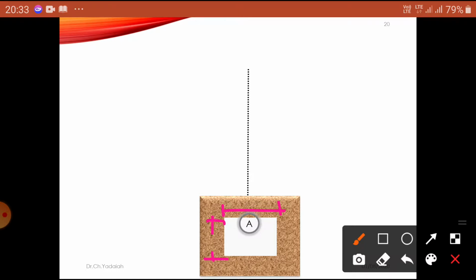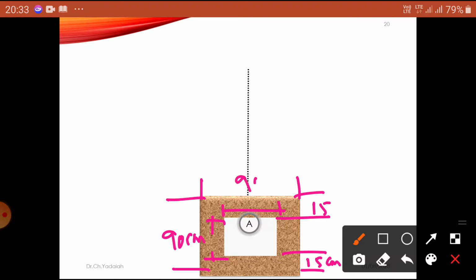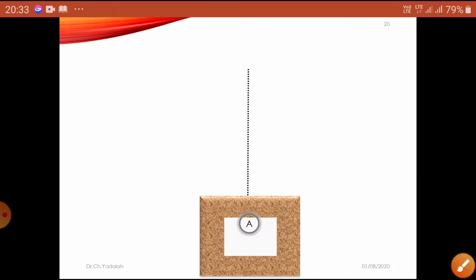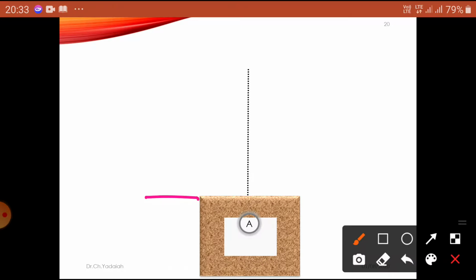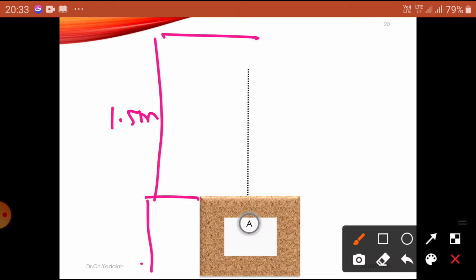At the same time, this is 15 centimeters and 15 centimeters, so 15 plus 60 plus 15 gives a total plate height of 90 centimeters. So the copper plate size is 90 by 90 centimeters. A good quality copper plate is used here, placed at a depth of nearly 1.5 meters, as you can see from top to here.